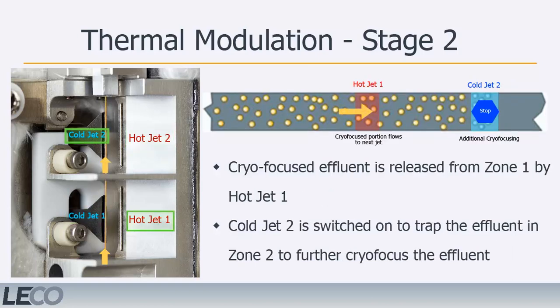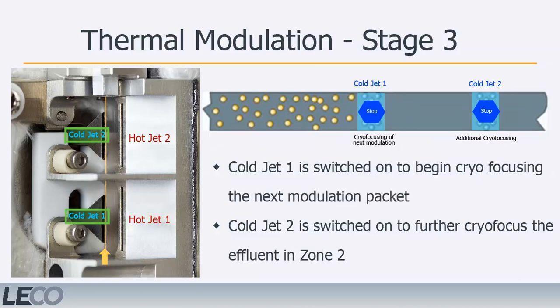During the second stage of modulation, the first stage hot jets will turn on to release the cryofocused effluent. Concurrently, cold jet 2 will turn on and trap the incoming effluent for further cryofocusing. In stage 3, both cold jets are turned on to allow the current modulation packet to completely focus onto the second jet. At the same time, the first cold jet will begin cryofocusing the next packet of column effluent.